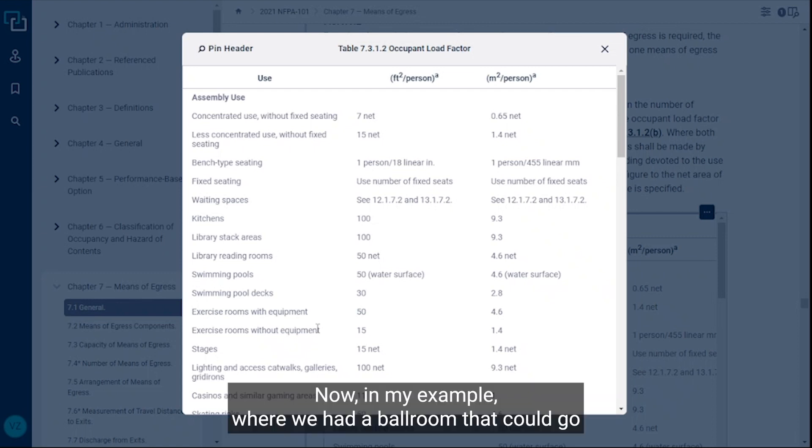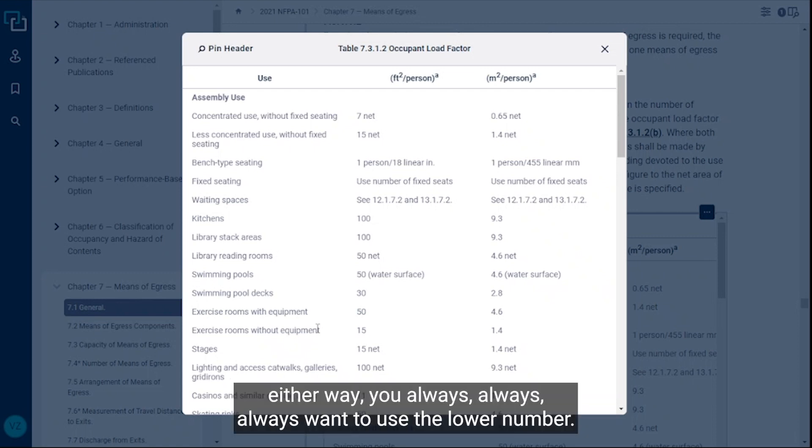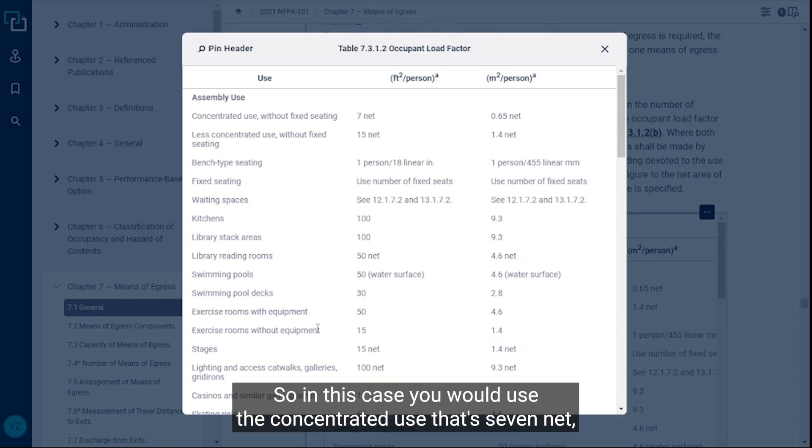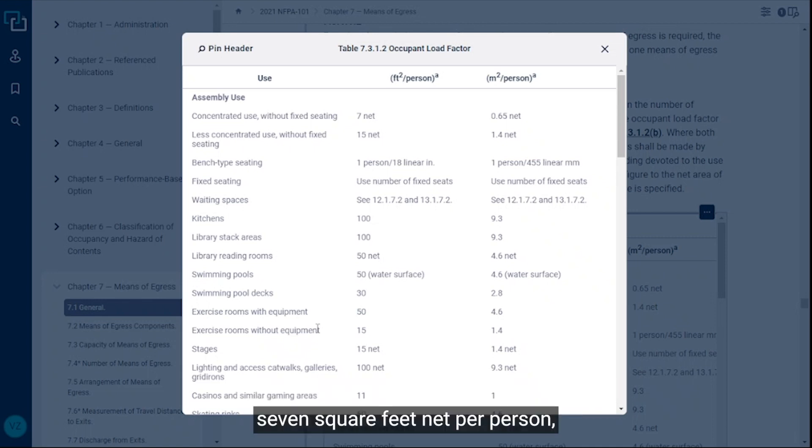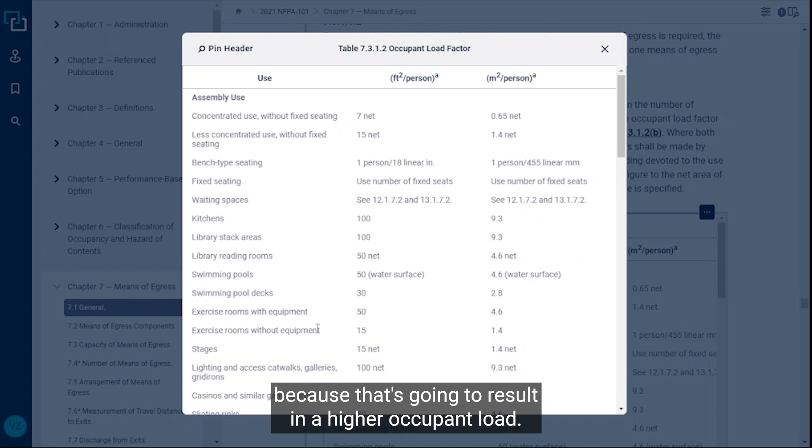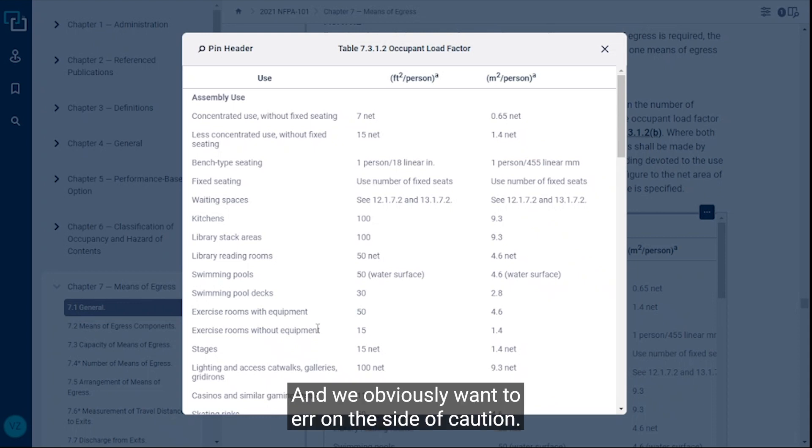In my example where we had a ballroom that could go either way, you always, always, always want to use the lower number. In this case you would use the concentrated use, that seven net, seven square feet net per person, because that's going to result in a higher occupant load and we obviously want to err on the side of caution.